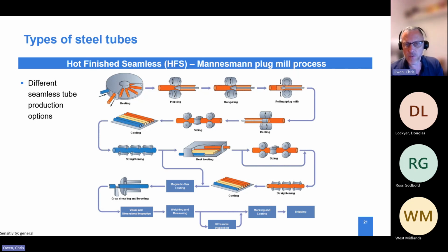The other thing is that on coil base, we're restricted to about 16 millimeters. If the coil is any thicker than that, we physically struggle to try to form that coil into a tube profile, whereas a seamless tube can be extruded or pierced with a very small internal diameter element, which then means you can get a tube with big outer diameter and very thick walls for very high pressure applications.